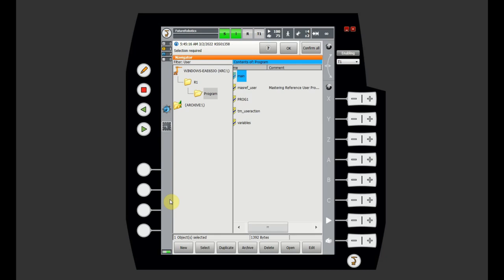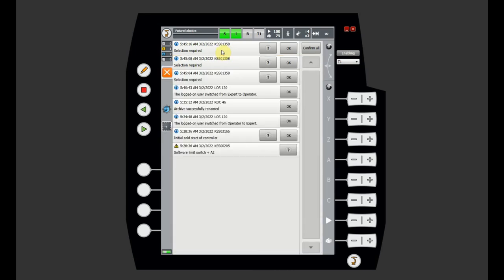One of the most important and probably most overlooked areas is the notification bar here. This is a key item to remember. Whenever there is a fault or something happens, don't just click Confirm All — that resets all active faults. You actually want to click and see what faults are currently on the robot, or what information the robot is trying to give you. There are actually five types of information that can be passed here, even though you only see four icons. The fifth type is dialogue messages, which require interaction with the operator and are not shown in this bar.